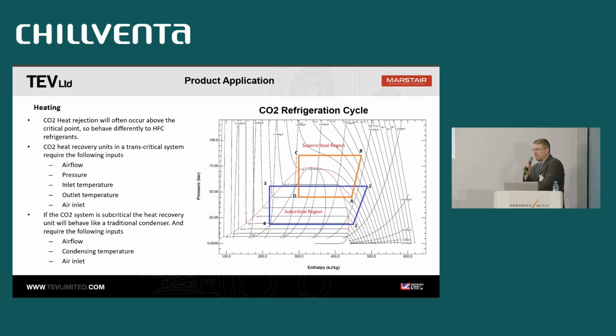If the CO2 is allowed to go subcritical, then it's very much like a condenser. If you're sizing a condenser for a refrigeration unit, similarly you just have the airflow and you work with the condensing temperature against the external air inlet. So it's very similar. You have your delta T that you'd size a condenser to relative to airflow, but on the air conditioning side internally. And that's how you generally would size the heating if you're subcritical.